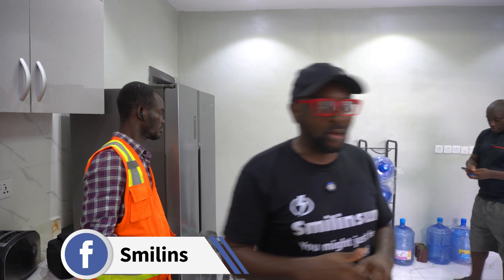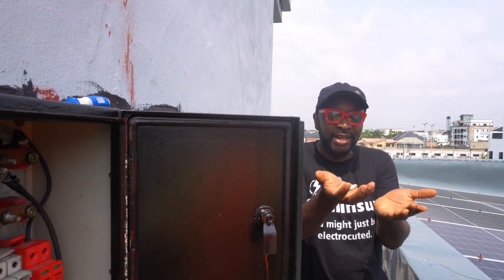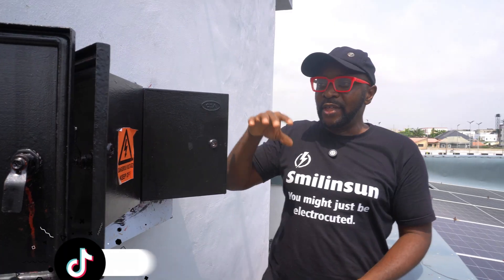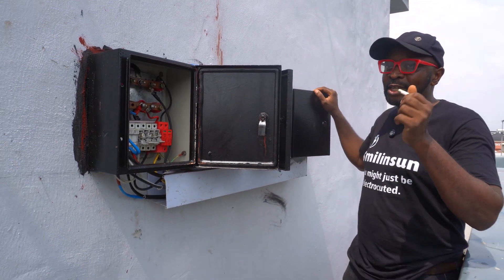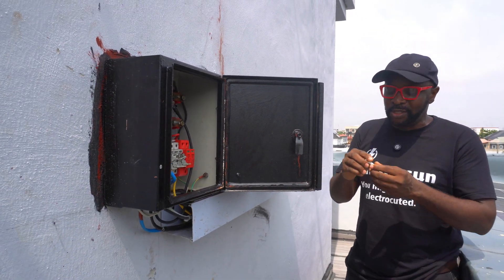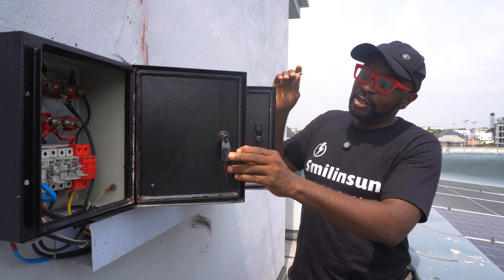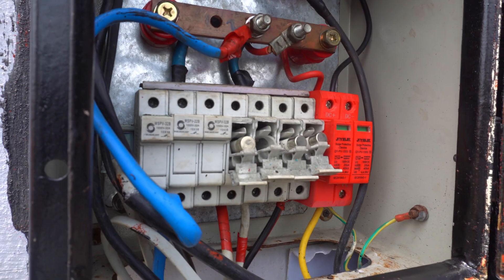The fuse is barely holdable — it is burning up. Thank goodness the boxes are outside the house, because this is a potential fire hazard. This is extremely hot, handling far more load than it's designed to do. We will need to change all of these fuses and put in the correct ratings for the job.